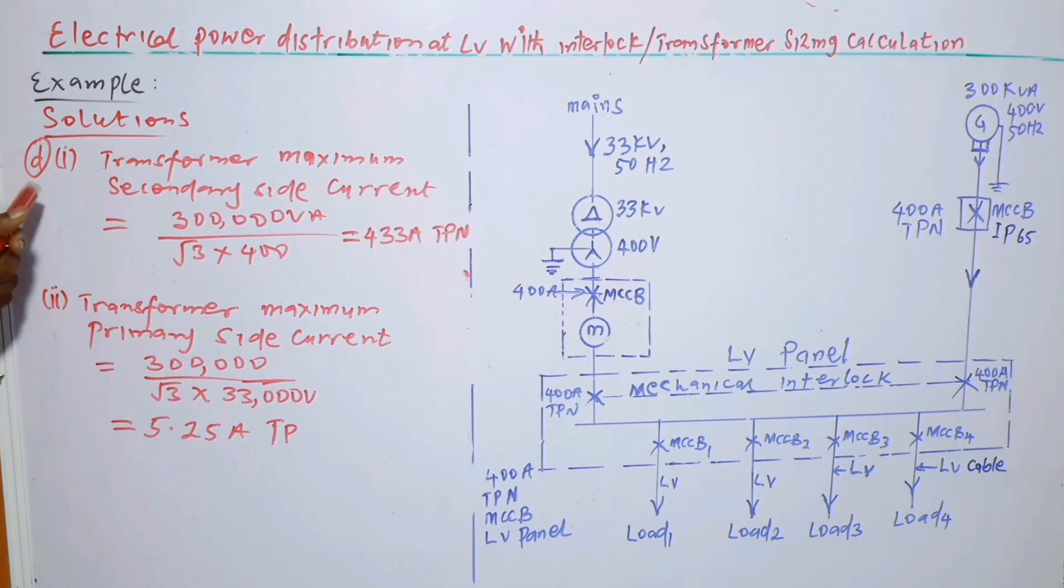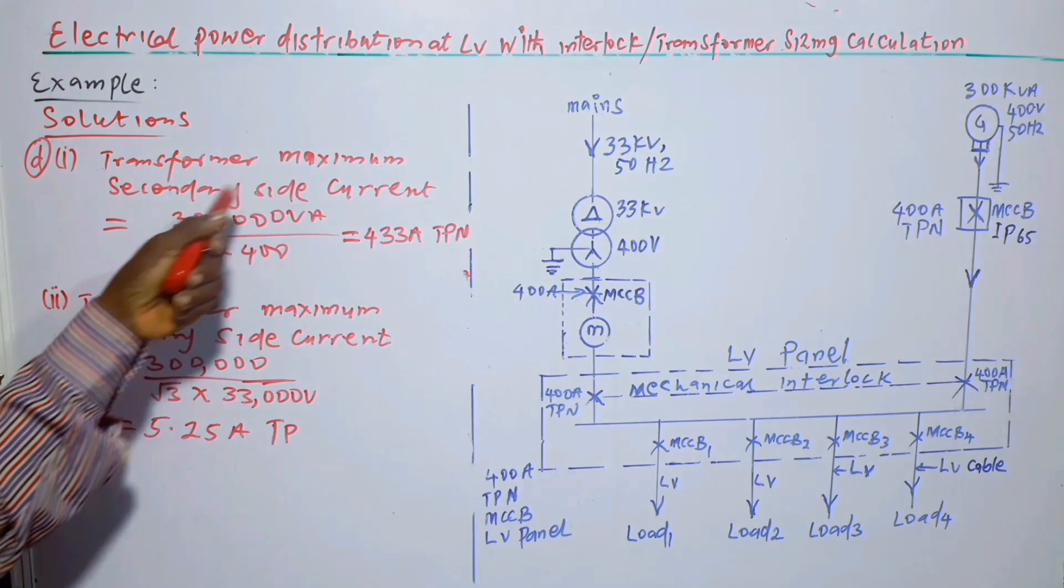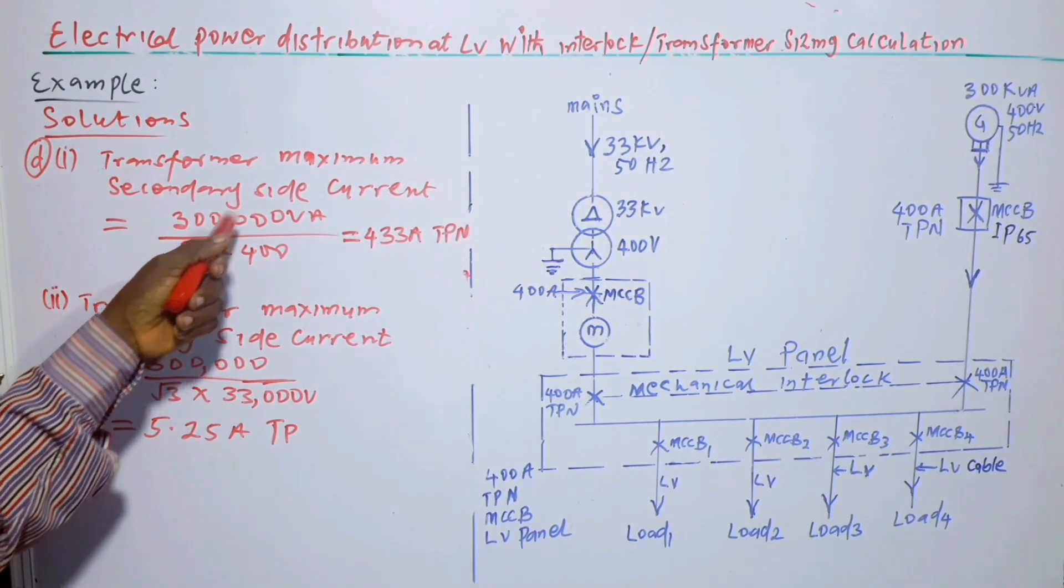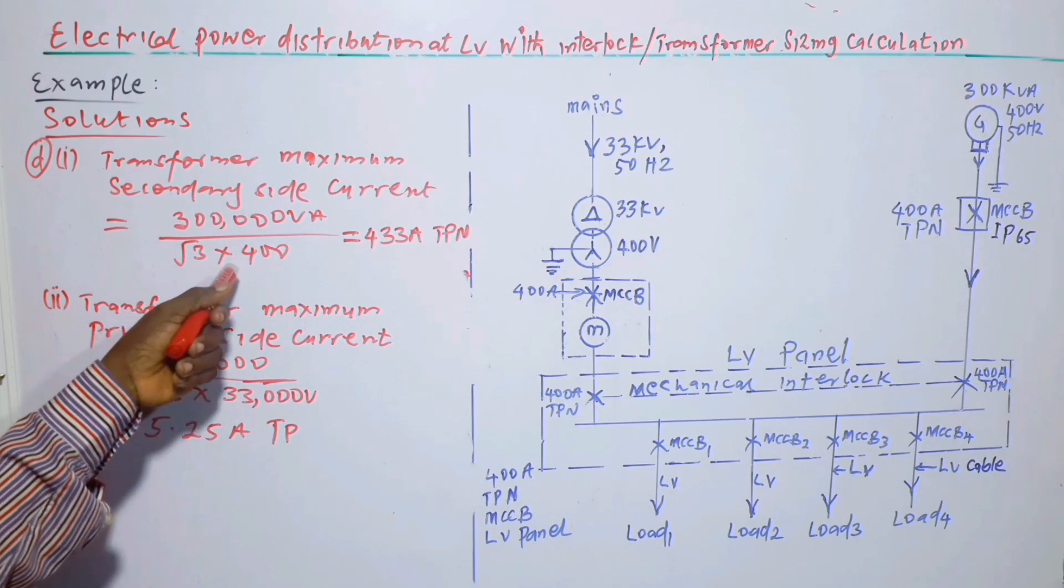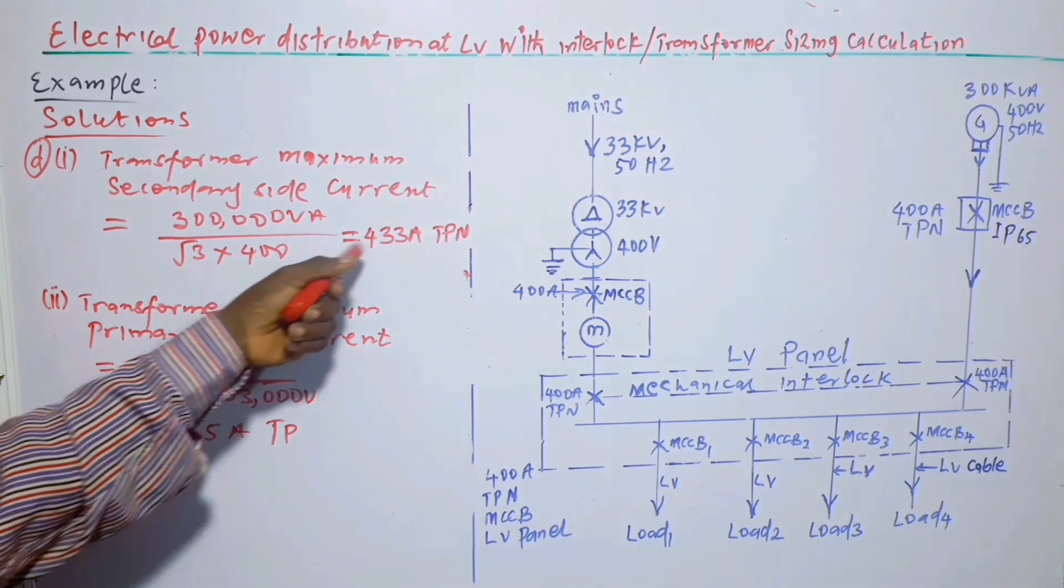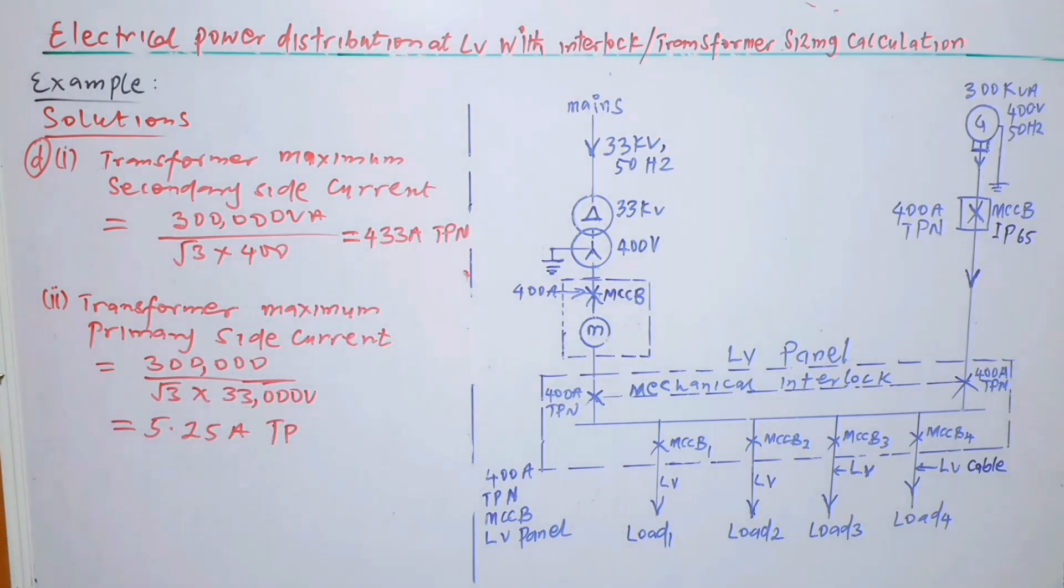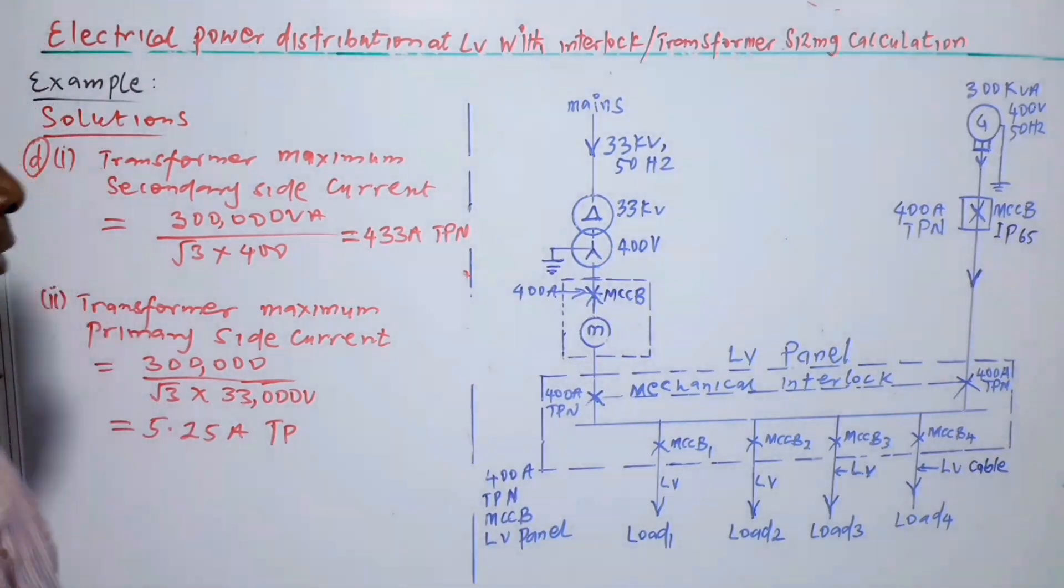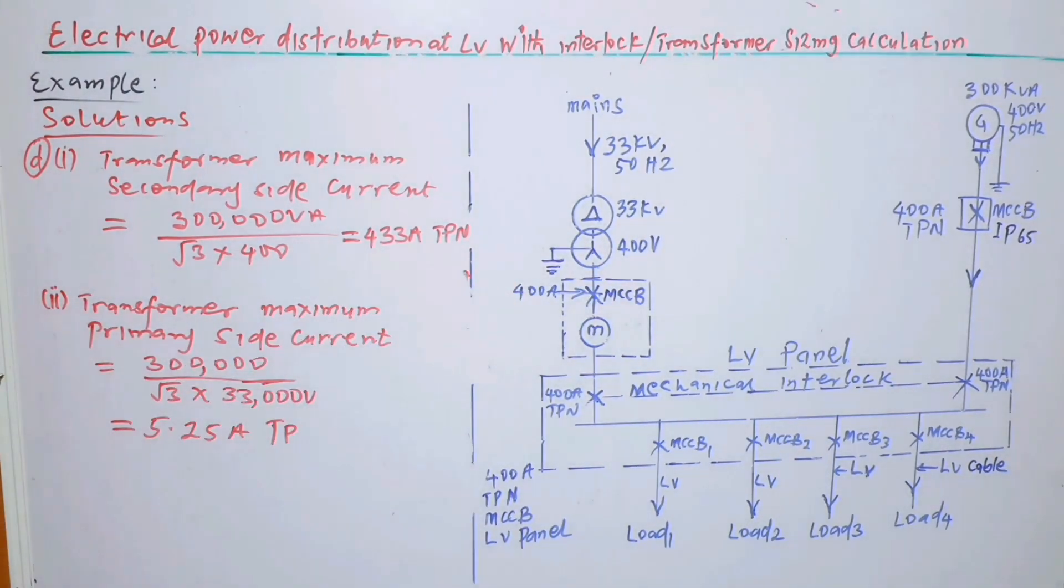So D part, one. Transformer maximum secondary side current is equal to 300,000 VA divided by root 3 times 400. And the answer is 433 A TPN. So we are talking of this star side. That's the secondary side.